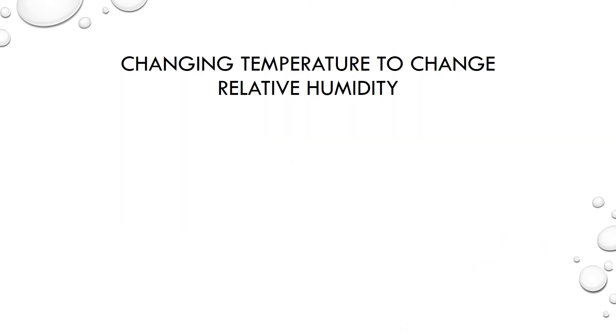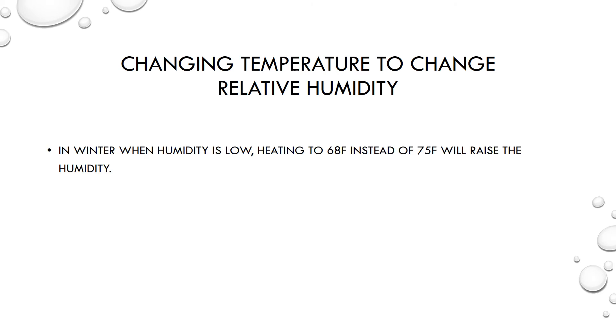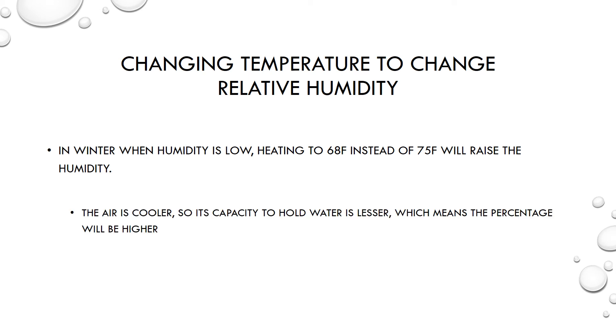The same concept applies for winters when it's cold and the humidity is low. Heating the air to 75 degrees would drive the humidity way down, well below what the already low outdoor humidity is. Heating to only 68 degrees instead would keep that relative humidity slightly higher because cooler air has a lower capacity to hold water. That same amount of moisture would take up more space at 68 degrees, giving a higher humidity percent, than it would at 75.